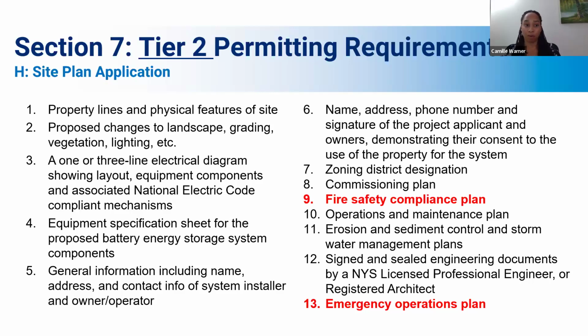The next is the emergency operations plan. In the event something goes wrong, you want a designated protocol and best practices for incident management. Your local first responders and fire officials want to know you're looking out for them, so this plan should be geared towards first responders—they should know where the deflagration panels are and whether or not they can use water. Work with the fire department to review this. It's not currently included or required by fire code, so we recommend including it as part of your application requirements.